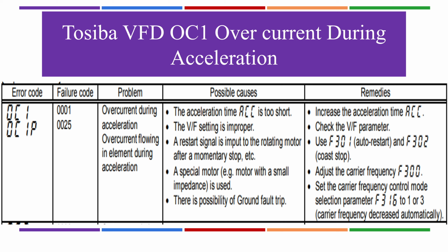Normally it happens for that reason, but these others also could be factors. So you just need to check that time if it is very short, and it depends on your application also. If the motor is big, then more acceleration time is required. If the motor is small, a short time will not cause the problem. But normally it happens when the acceleration time is very short on a big motor or big VFD.